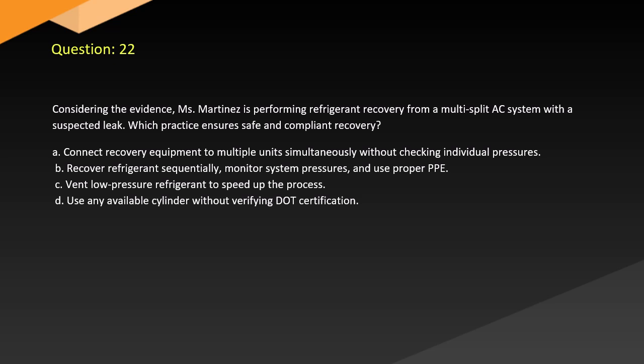Question 22. Considering the evidences, Martinez is performing refrigerant recovery from a multi-split AC system with a suspected leak. Which practice ensures safe and compliant recovery? A. Connect recovery equipment to multiple units simultaneously without checking individual pressures. B. Recover refrigerant sequentially, monitor system pressures, and use proper PPE. C. Vent low-pressure refrigerant to speed up the process. D. Use any available cylinder without verifying DOT certification.